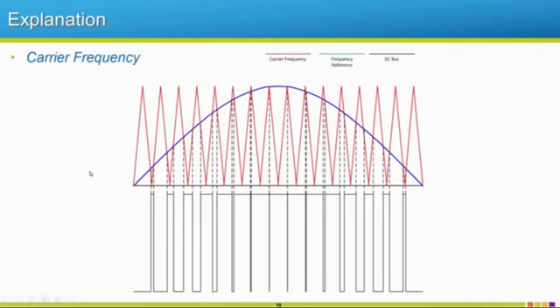So how this works is this carrier frequency set. So it has a set area that it works in, but depending on what frequency reference we want, we will just choose our intersecting points from there that picks how wide of a pulse we need. As our wave starts to build up, our intersecting points get a little wider. So that's why our pulse gets larger and so on, up until where we saturate, we're on the whole time. And then we start to come back down. These points of intersection start to get smaller and smaller. And that's how we would make for this example, an upper part of one of our waveforms.